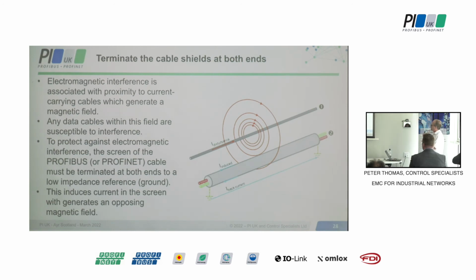So, this is basically what we've got here then: we've got some kind of source. There is a magnetic field around it. We've got our particular shielded cable, and if we connect our shield at both ends to this common reference, basically a current will be induced in that shield, and it creates an opposing magnetic field which gives us the shielding effect.